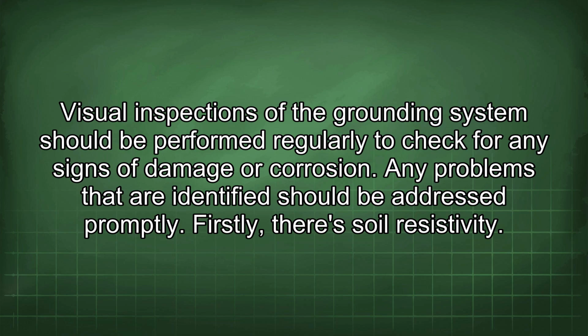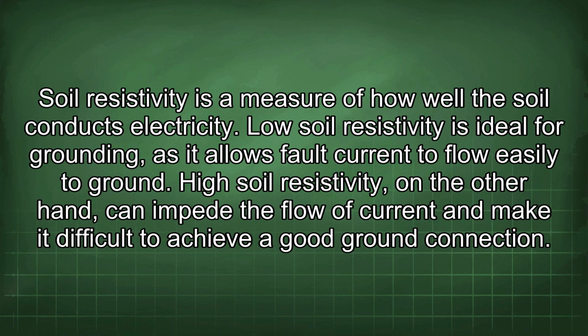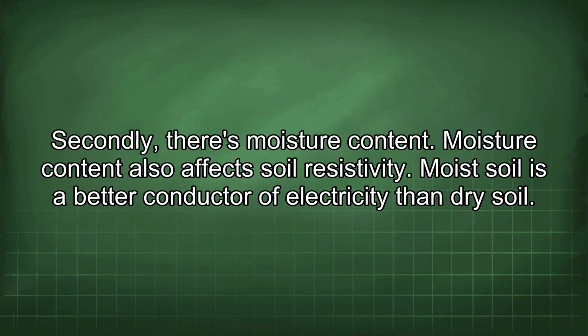Firstly, there is soil resistivity. Soil resistivity is a measure of how well the soil conducts electricity. Low soil resistivity is ideal for grounding, as it allows fault current to flow easily to ground. High soil resistivity, on the other hand, can impede the flow of current and make it difficult to achieve a good ground connection. Secondly, there's moisture content.